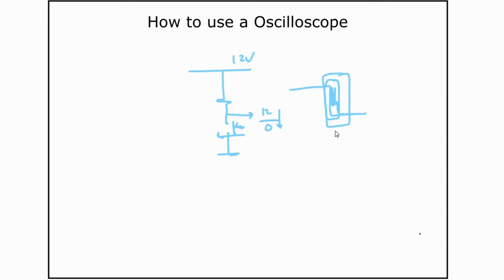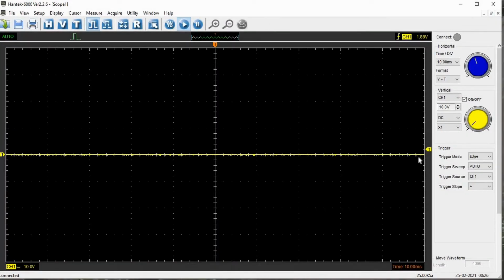So now let's set it up for this. I have hardware that has been set up like this, and this point I have connected to channel 1. Now let's see how to capture this moment. Till now our capture was continuous, meaning we were continuously triggering and holding. Now what we will do here is a single shot capture. For that, first we have to make sure that it is working properly, like the transition is happening.